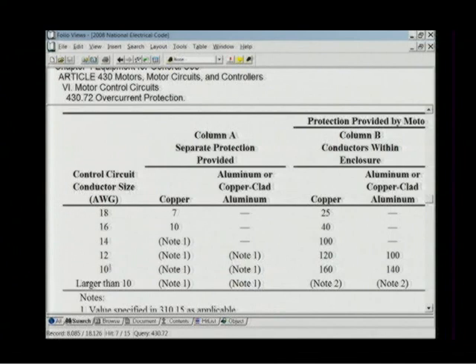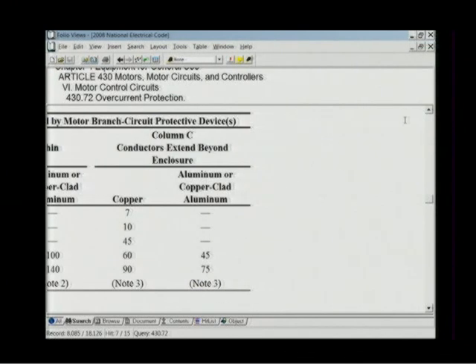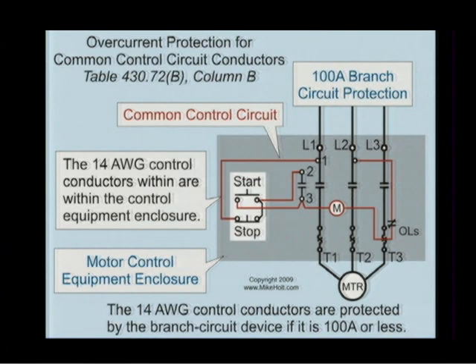So 18, 16, 14, 12, 10. So if I'm going to be using 18 gauge wire, the maximum the branch circuit protection device could be for the motor, short circuit ground fault, is 7. 16 gauge wire is maximum 10. But if I then go to a 14 gauge wire, I could use 45 amp branch circuit protection for the motor. If I had a 12 gauge wire, I could use those conductors. So a 12 gauge wire is only good where the branch circuit short circuit protection does not exceed 60 amperes if I extend this out.